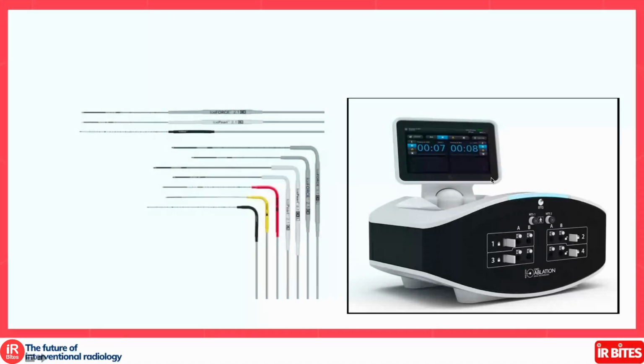You can set the mode to freezing or thawing. You can set the time for it. And on this, you can connect up to 8 needles, so 2 on each port. And they've got a wide variety of probes, as demonstrated here. And each of these probes, they have literature showing you what shape and size of the ice ball you can expect to form. Each probe will produce a different shape and size of the ice ball.